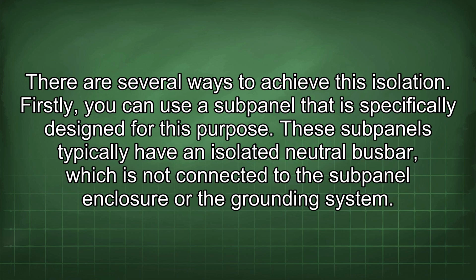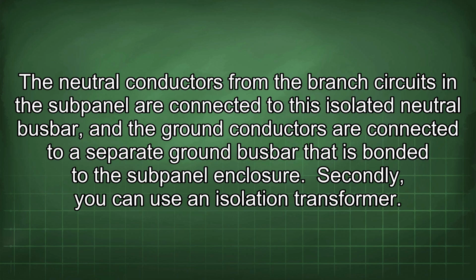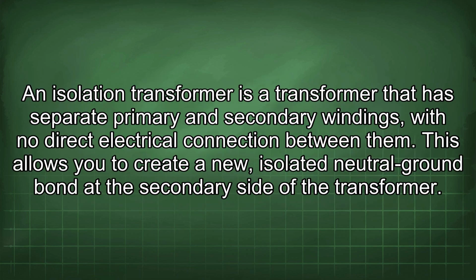These subpanels typically have an isolated neutral busbar, which is not connected to the subpanel enclosure or the grounding system. The neutral conductors from the branch circuits in the subpanel are connected to this isolated neutral busbar, and the ground conductors are connected to a separate ground busbar that is bonded to the subpanel enclosure. Secondly, you can use an isolation transformer. An isolation transformer is a transformer that has separate primary and secondary windings with no direct electrical connection between them. This allows you to create a new, isolated neutral ground bond at the secondary side of the transformer.